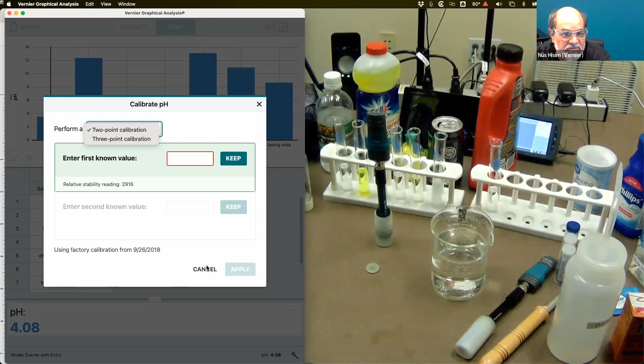If you did them in a narrow range, it was fine. But if you tried to do it over a wide range, the calibrations weren't so great. So the GoDirect sensors now give you the option to do a 3-point calibration. In the software, if you go to the calibrate option, it gives you a 2-point and a 3-point calibration option. So you can really improve the accuracy of the sensor if that's something that you want. When you do a calibration of a GoDirect sensor, either in Graphical Analysis or on a LabQuest, the calibration gets stored to the memory of the sensor. So once you've done it, unless you've really done something nasty to the probe, you don't need to do it again.